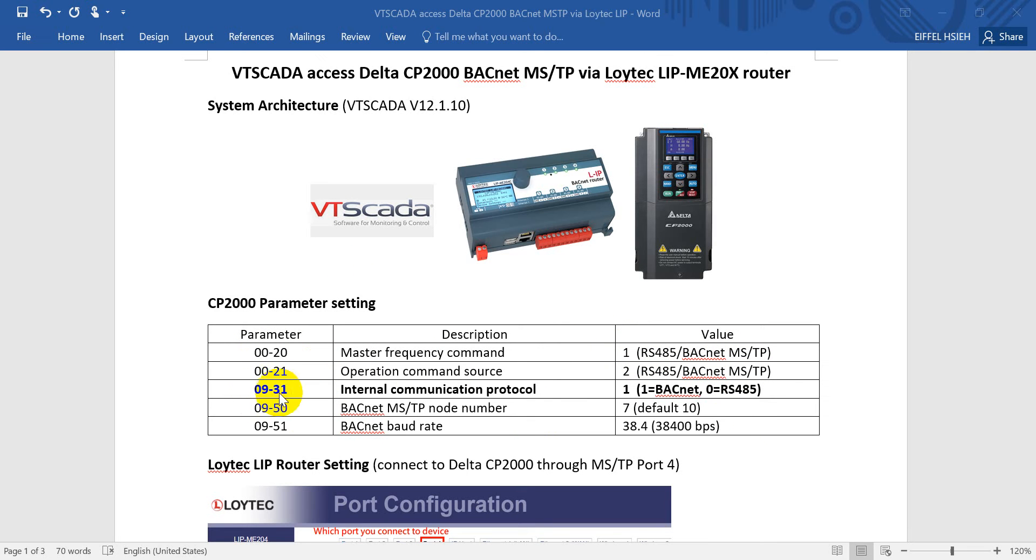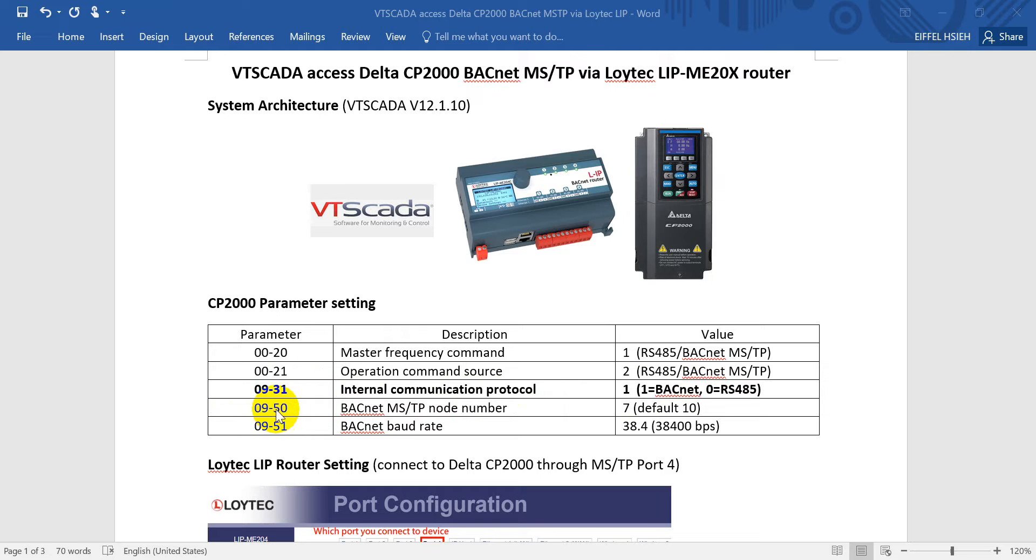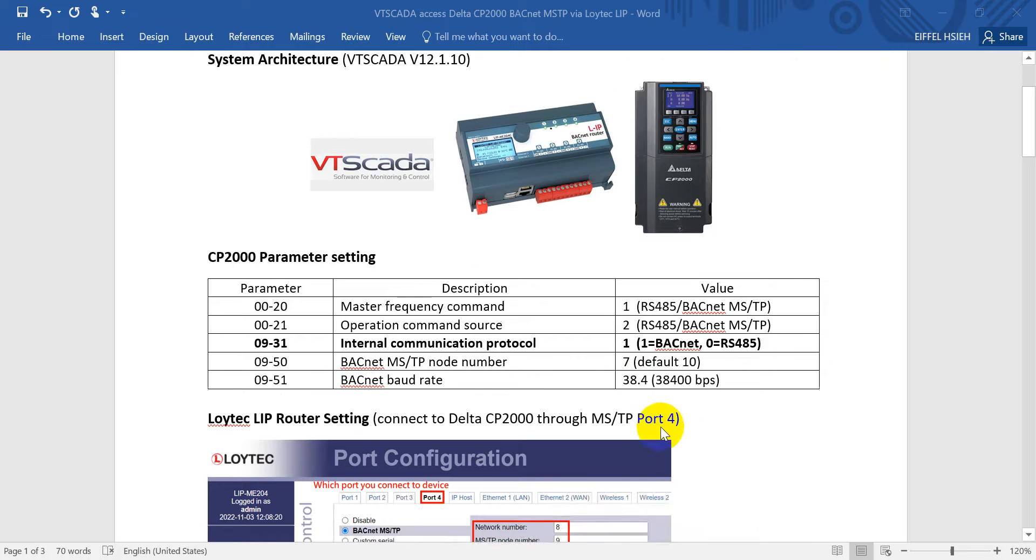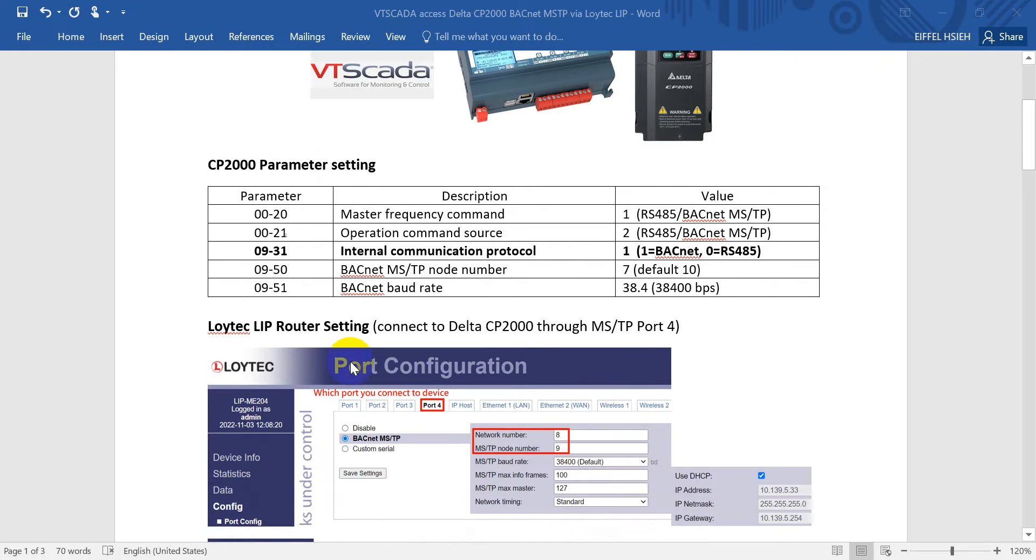Remember to modify parameter 09-31. This one is the internal communication - one means BACnet. Then make sure to set the correct BACnet MSTP node number for CP2000, and then the baud rate.